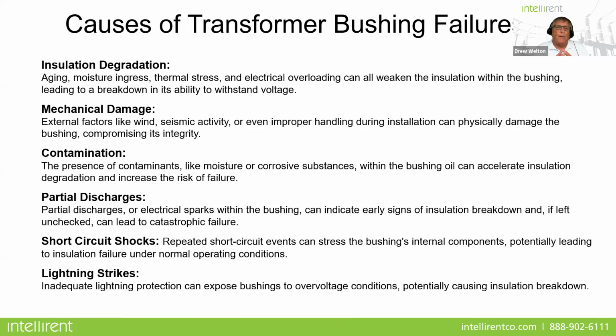Now, what are some of the common failure issues surrounding bushings? Well, first and foremost, insulation degradation. Aging, moisture ingress, thermal stress, and electrical overloading all weaken the insulation within the bushing, leading to a breakdown of its ability to withstand the voltage. You can have mechanical damage: things like wind, seismic activity, and improper handling during installation can physically damage the bushing, compromising its integrity. Contamination: the presence of contaminants, excessive moisture, corrosive substances.